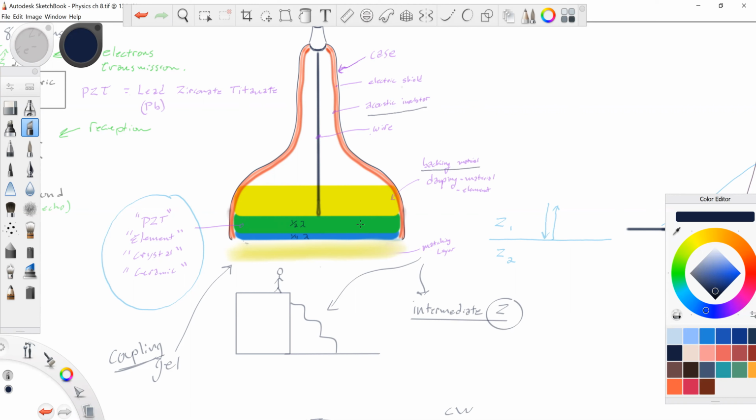Okay. So high degree of sound absorption, and an acoustic impedance similar to the PZT. Well, why? Because you actually want the sound not necessarily to bounce back and forth here. You do want the sound to go in here. You just want it to be completely absorbed. Impedance of damping element similar, so the sound wave created moves into the damping element and away, absorbed.